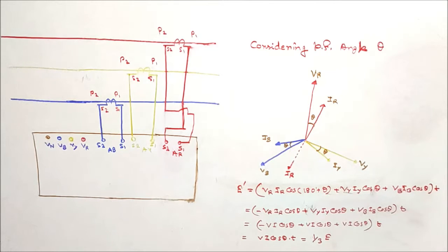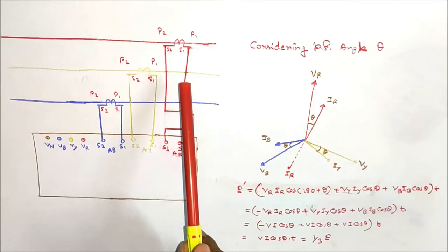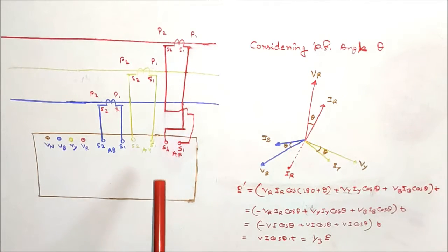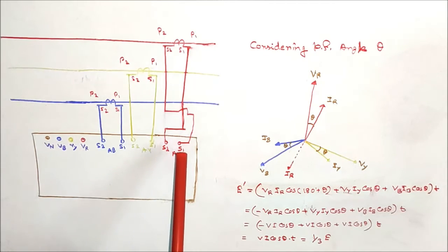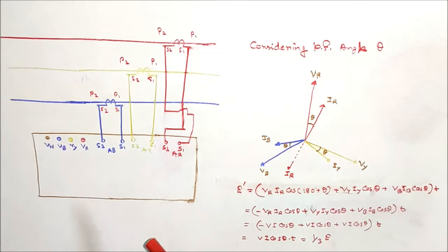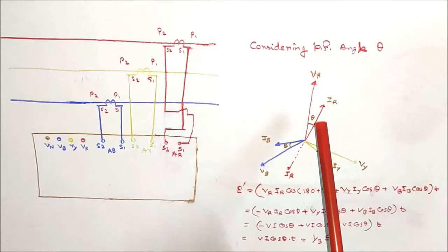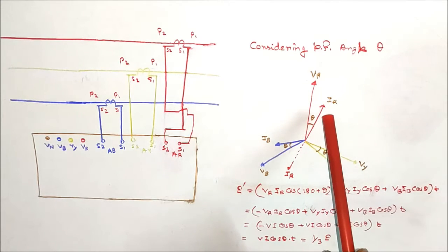Now consider the case when any phase CT polarity is reversed in the energy meter reading. Here the red phase CT polarity is reversed — that is, the S1 terminal of the CT secondary side is connected to the S2 terminal of the red phase coil of the energy meter, and the S1 terminal of the energy meter is connected to the S2 terminal of the CT.